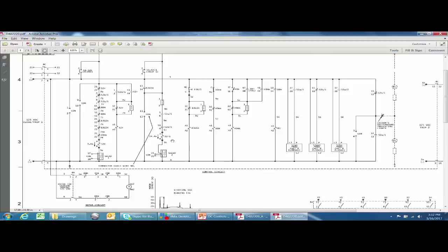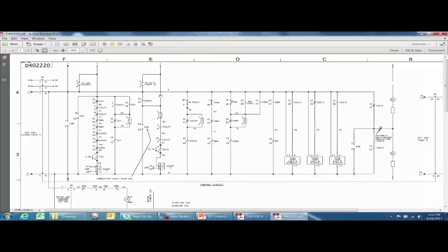That's the closed circuit. Here is the first of the trip circuits — here is a trip coil. Notice you don't want to energize the trip coil unless the breaker is actually closed, so we supervise it with a couple of 52A contacts. Notably there's nothing else in this circuit. While the close circuit requires a whole bunch of features to be just right before you close the breaker, once a breaker is closed and there's a problem, you want to make sure that breaker trips without any chance of failure.